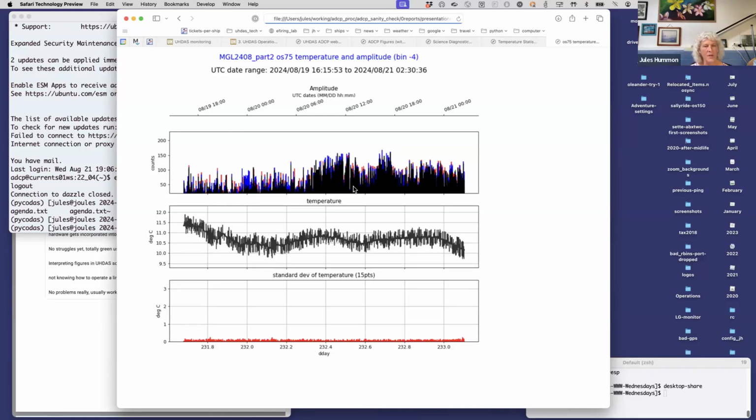The temperature seems to be a canary in the coal mine about electrical noise of the instrument. So this fuzz is a lightweight level of some kind of electrical noise getting into the analog cable. It's not affecting the velocities, but if you have spikes that are like 20 or 30 degrees, then that means you do have an electrical noise problem, and you are probably going to see degradation of the velocities.